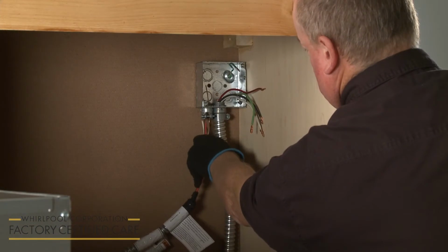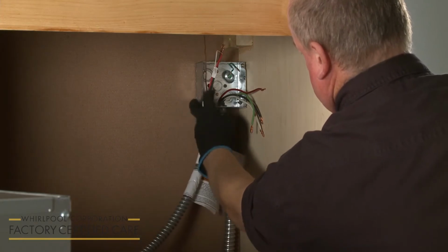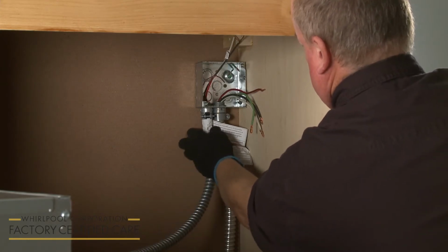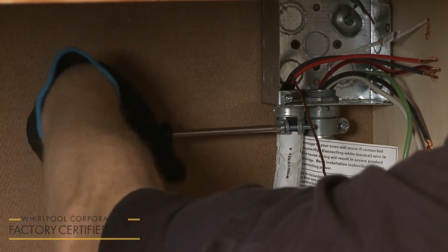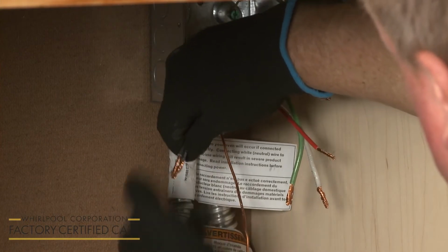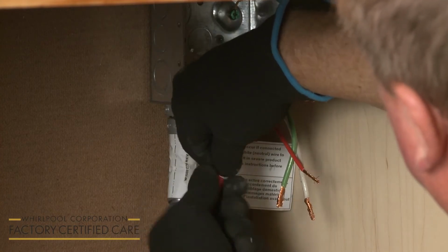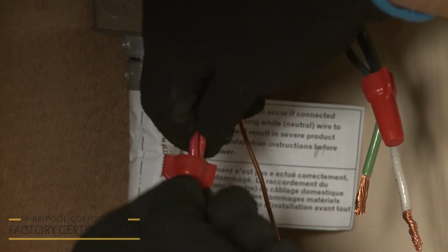Use a UL-listed or CSA-approved 1/2-inch diameter conduit connector to connect the flexible cable conduit from the microwave oven to the junction box. Tighten the screw or screws to secure the conduit. Now join the black wires together and secure them using an approved UL-listed wire nut. Do the same to secure the 2 red wires together and the 2 white wires.